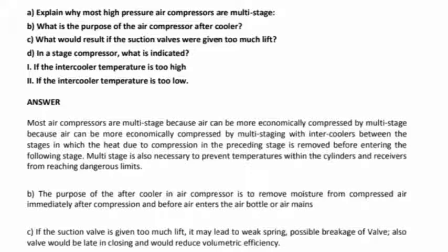Multi-stage is also necessary to prevent temperature within the cylinders and receiver from reaching dangerous limits, and this prevents risks of fire and explosion, prevents lubrication problems and carbon buildups on valves, and also reduces thermal stresses as well as increases the lifespan of the air compressor.